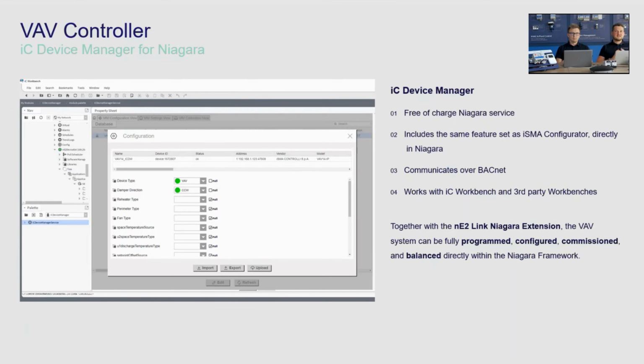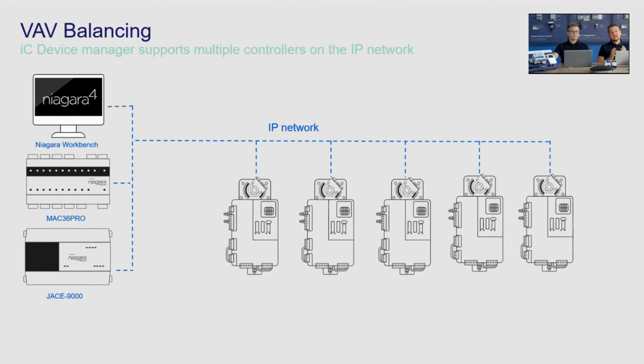So it means at the end of the day, if things change during the commissioning process or the building grows, you can always export the settings from the latest configuration of your VAV box and import them to the new boxes you have recently added to your facility. So it's also free of charge, as I mentioned, same feature set, and works with all. So together with our AnyTool, which is a programming tool that we'll tell you a bit more about in a second, you can really configure, commission, balance, and program the controller or extend the program in your VAV unit directly using the Niagara framework. So that's how it looks.